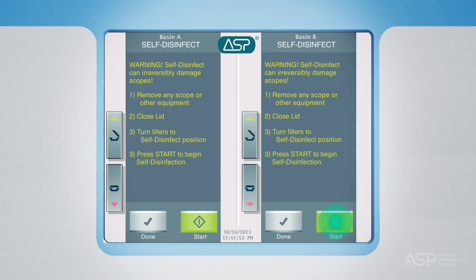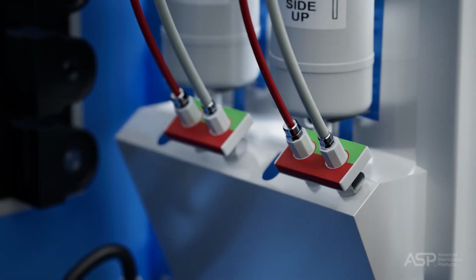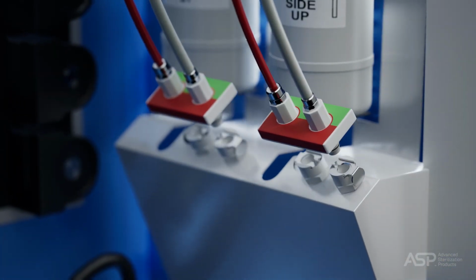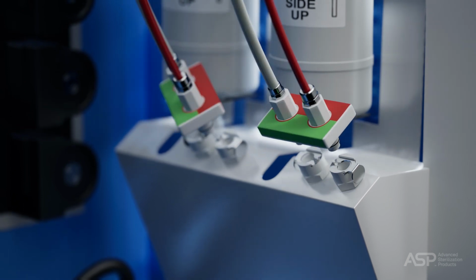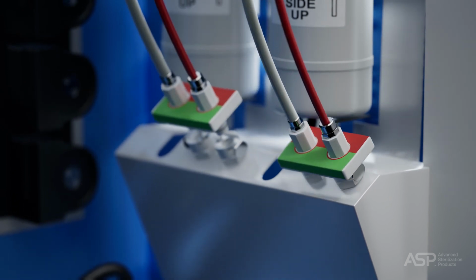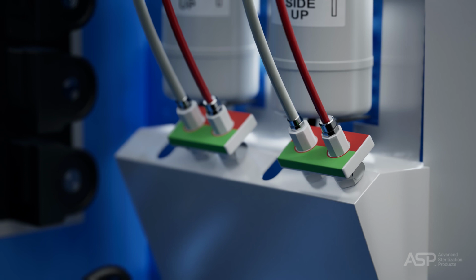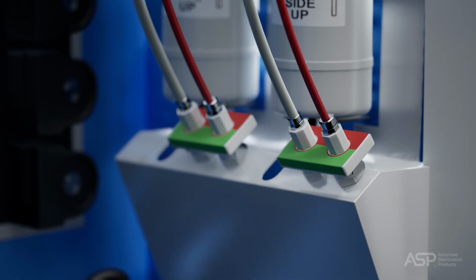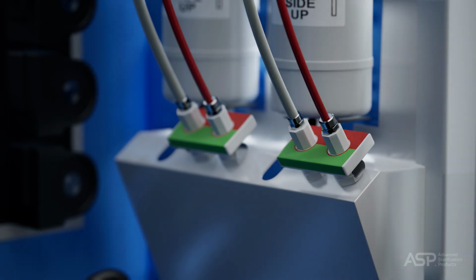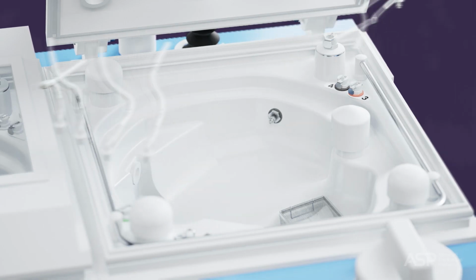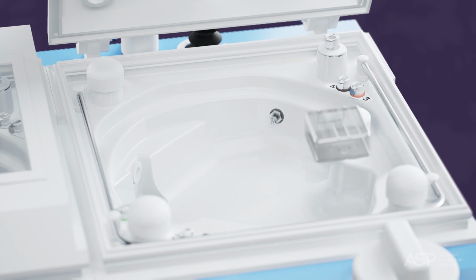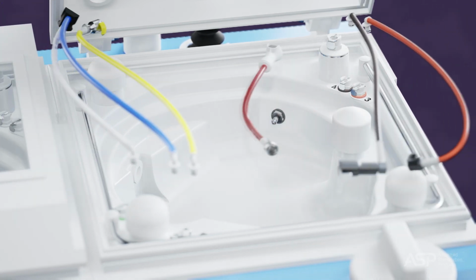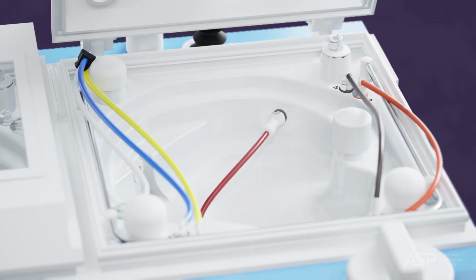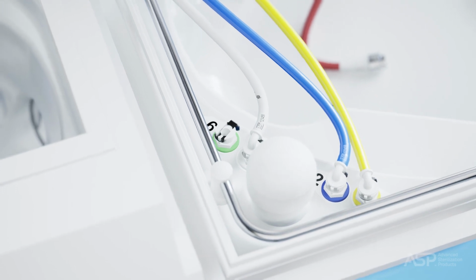self-disinfect cycle. When the self-disinfect cycle is complete, turn the quick disconnect fittings 180 degrees back to the setting with the green portion of the label facing left. Check closely that both fittings have been snapped into place properly. There will be 2 noticeable clicks on each fitting when properly seated. Remove the clear connectors and store until the next use. Then reattach the color connectors so that the system will be ready to run the next reprocessing cycle.